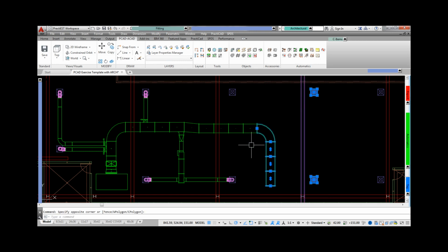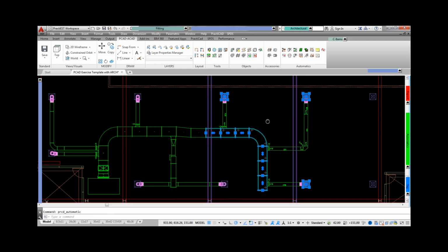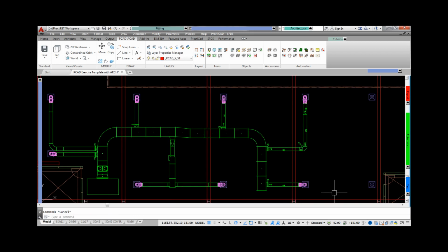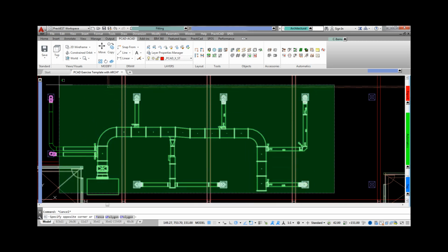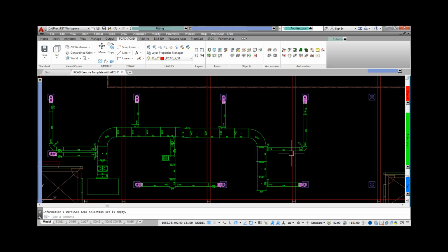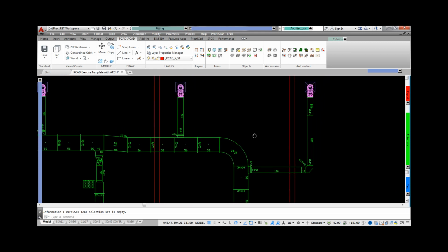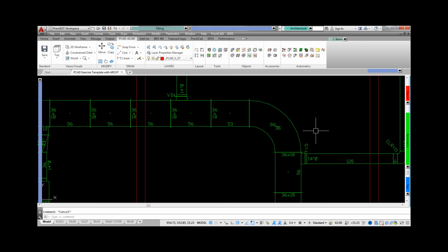You can run as many of these at once as needed, and there's truly a lot of scenarios to choose from. In this next example, we're choosing between two choices. The first route is one turn at 90 degrees. The second route uses two turns with 45 degree elbows. If the engineer requires a hard pipe connection or doesn't allow for you to bend flex on the GRD, then simply adjust your route accordingly. Hard pipe options and options that require an elbow, no matter how far the drop, are available.